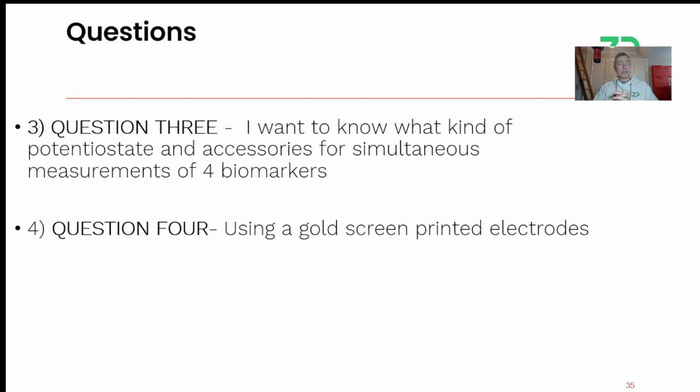The currents that you are passing are massive. There's something going wrong here, and unfortunately it's not on the SPE. I suspect it's on the connector. Primarily, it's on the connector before you start troubleshooting that potentiostat, but primarily it's the connector. Until you sort that connection out, you can't troubleshoot anything else.